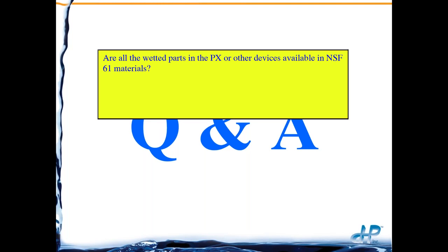Are all wetted parts in the PX or other devices available in NSF 61 materials? The Q300 PX is fully NSF 61 certified — those are the devices installed at the Carlsbad seawater RO plant, where I believe NSF 61 was a requirement. Other devices — Pelton wheels and turbochargers — to my knowledge do not have NSF 61 certification. It would only be the Q300 of the PX series.